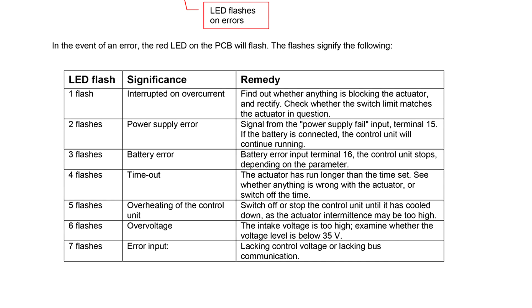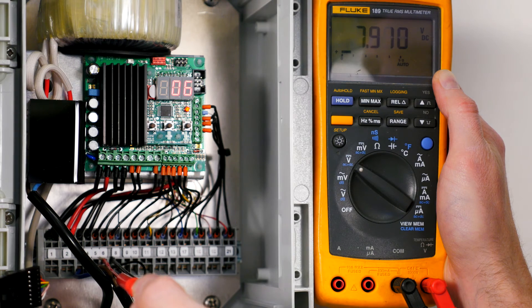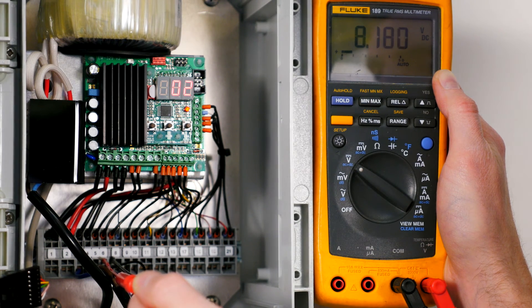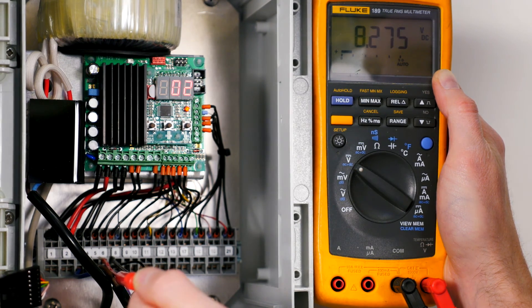If the display value does not change, it may be due to errors in the feedback from the actuator. If you cannot run the actuator with arrow up-down, you may make an adjustment of the upper zero point with a voltmeter mounted.